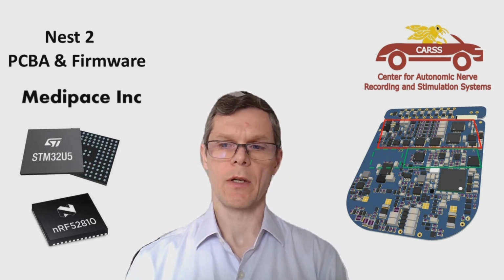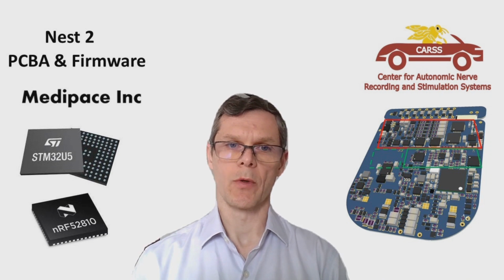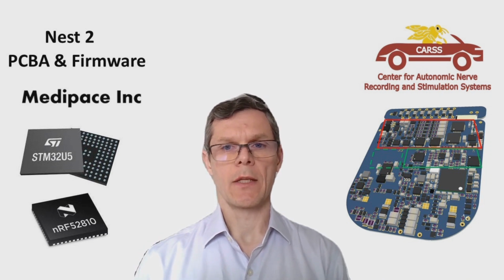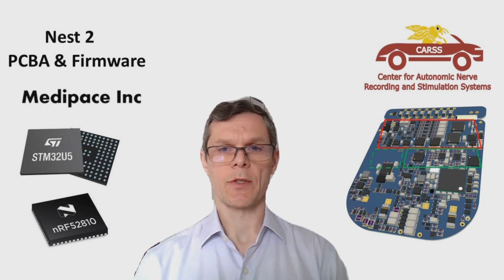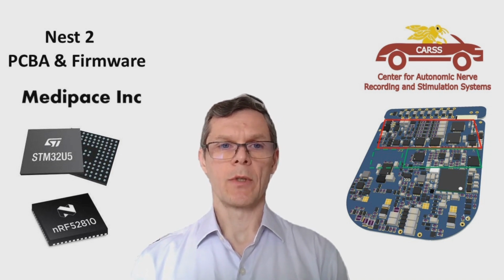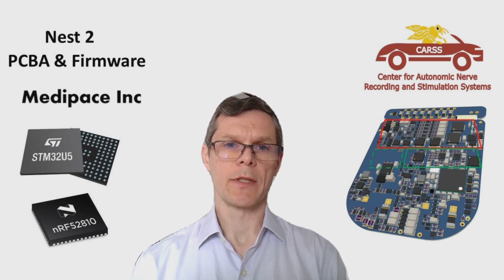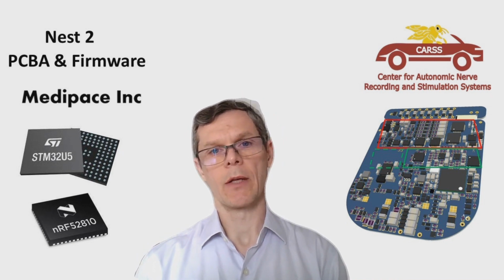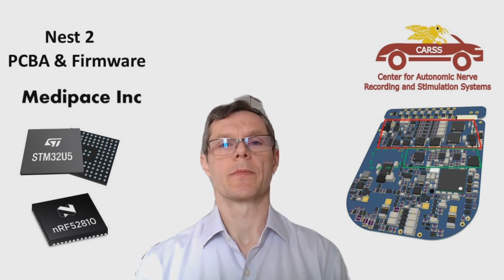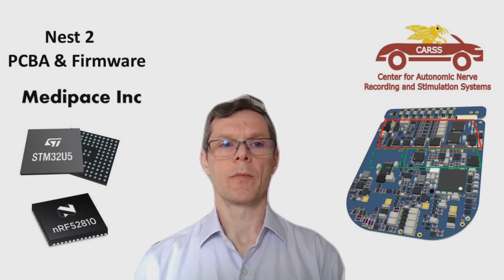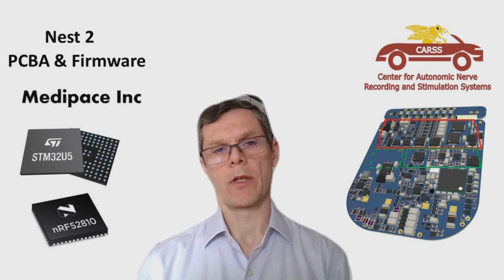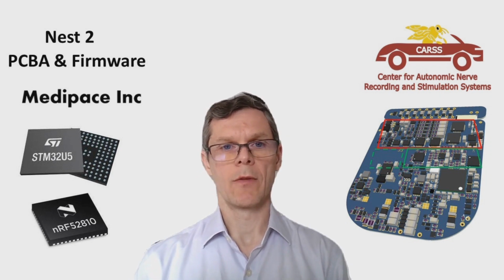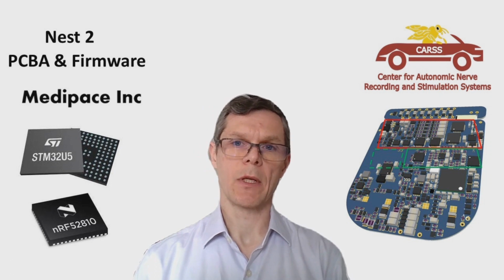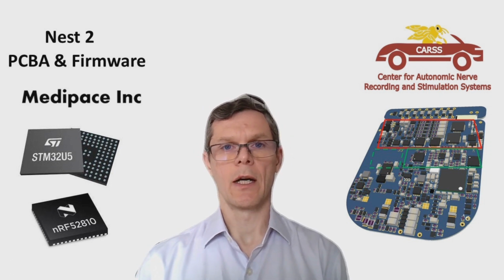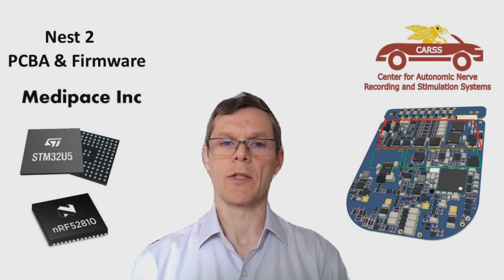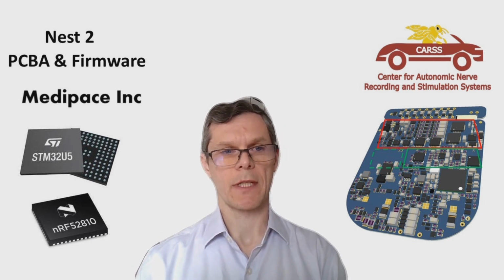So first, we are planning to use low power, low noise, and small size. And in order to do that, we have selected the chips, as you can see on my left, which have several low power modes, including some that are below 1 microamp and also use automatic voltage regulation. Also, we are planning to use full fail-safe operation of the PCBA for long-term reliability. To do that, many circuits have redundant components and redundant ways of controlling them, and also methods for assessing their proper function.